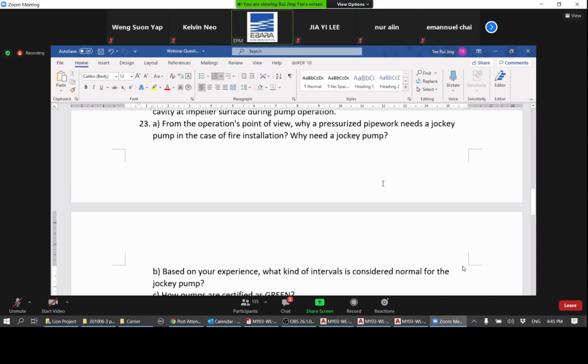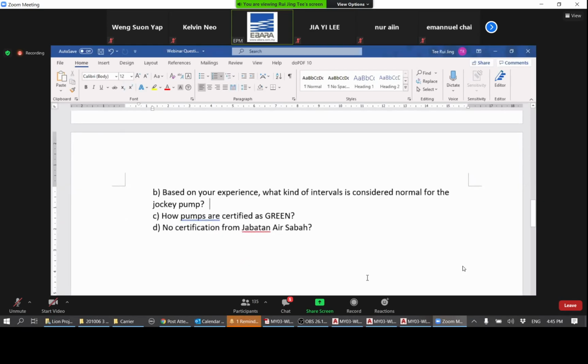Okay, so based on your experience, what kind of interval is considered normal for the jockey pump? I'm not sure what you mean by intervals here. Are you referring to the flow rate or the start-stop? If you're talking about the flow rate, then it's probably 5% of the total flow rate of the main pump. That would be good enough. There's no formula for this. Usually it's just based on what you feel would be the leakage rate of the pipework, of the pipeline.